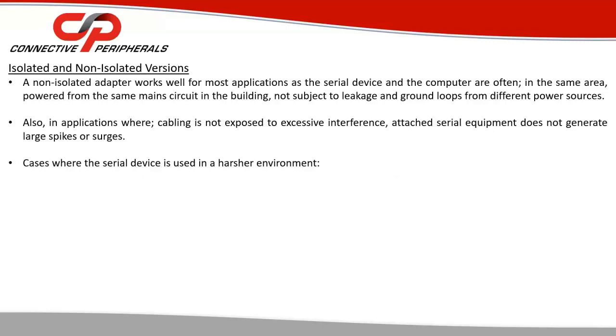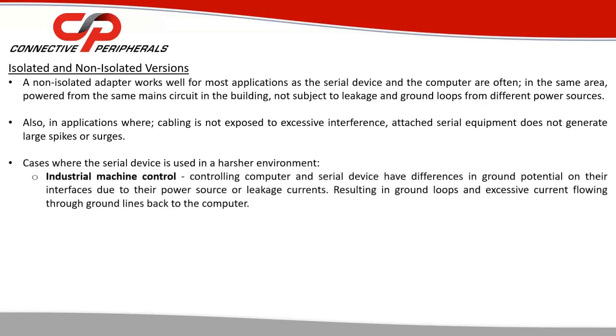Some examples include applications such as industrial machine control, where the controlling computer and the serial device may have differences in ground potential on their interfaces due to their power source or due to leakage currents. This can result in ground loops and excessive current flowing through the ground lines back to the computer.